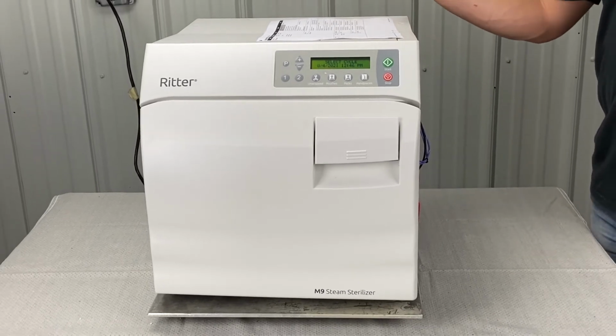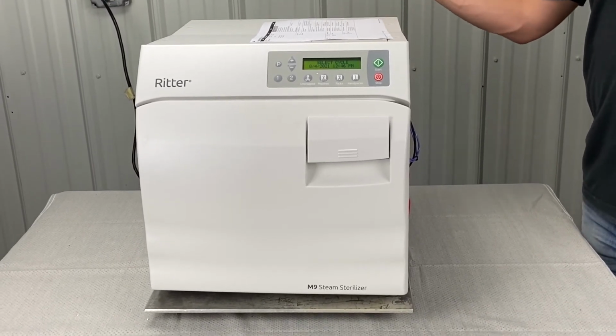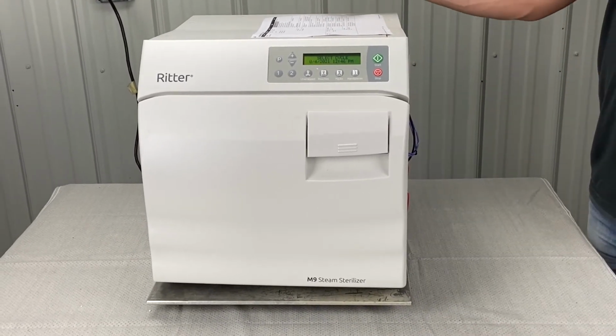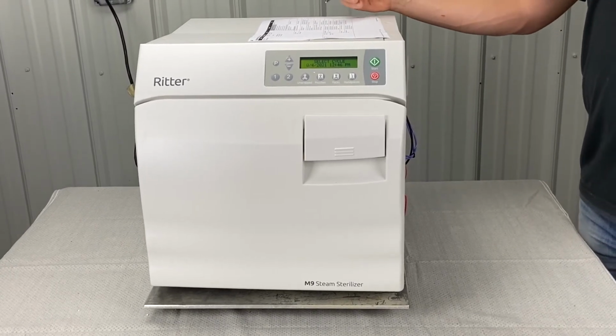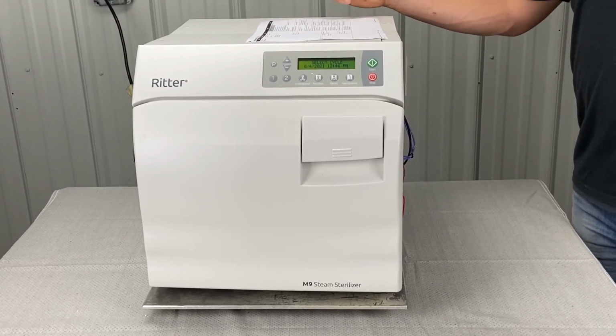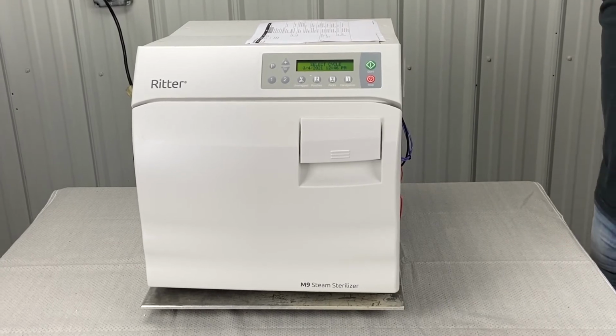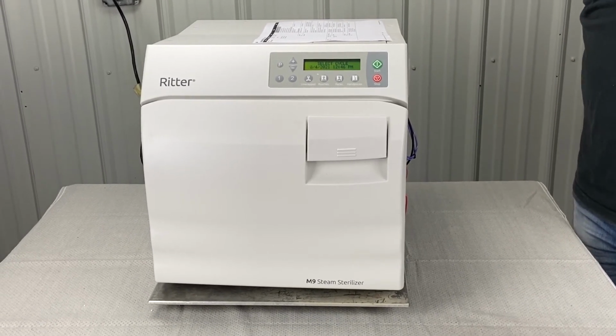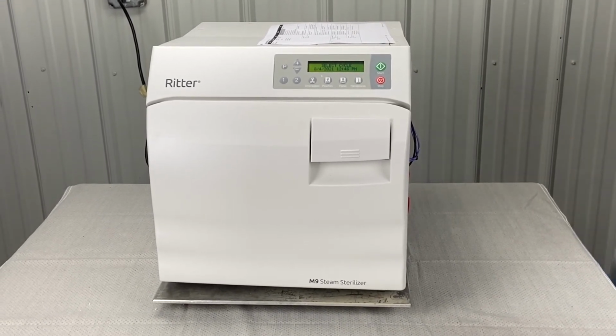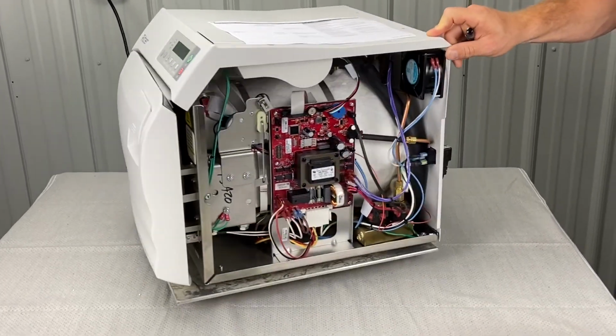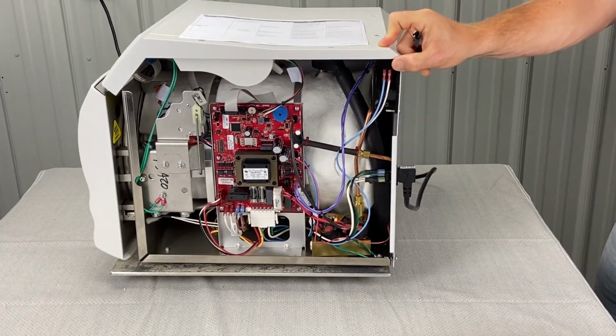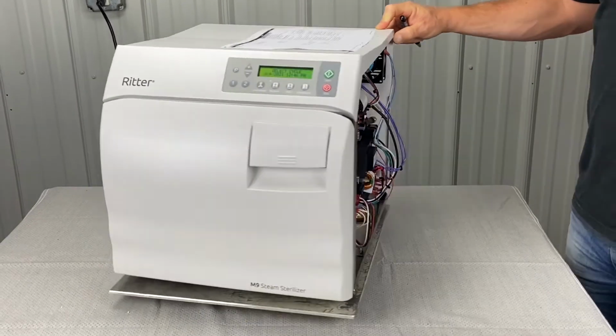So make sure your chamber filter is not clogged. That is part of your weekly maintenance. That's in a different video. If pressure is above 7.72 psi, check for blockage in the pressure sensor tubing between the PC board and the chamber. That's kind of what I just talked about. So that covers Charlie 326 error code.